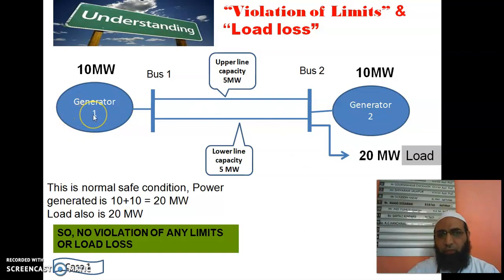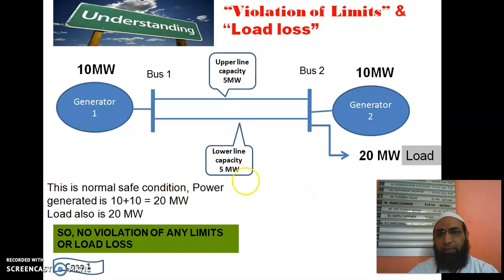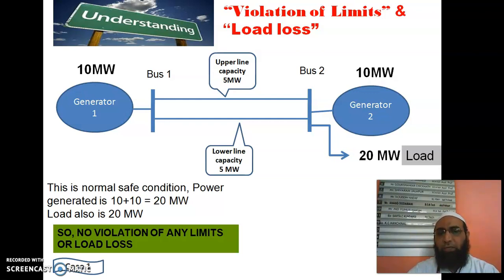We have two generators: generator 1 with a capacity of 10 megawatt and generator 2 which can generate 10 megawatt. There are two buses, bus 1 and bus 2. The upper line capacity is 5 megawatt and the lower line capacity is 5 megawatt. The load required is 20 megawatt. In this normal condition, the two generators produce 10 plus 10 equals 20 megawatt, matching the load. There is no violation of any limits and no load loss — this is a safe, secure condition. This is case 1.